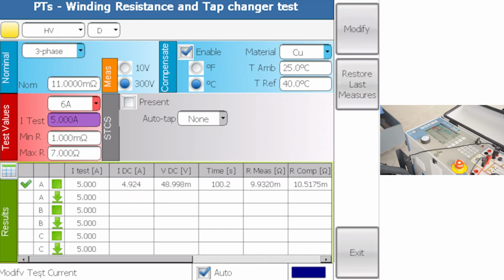All right, we've measured the resistance. So the measured resistance is 9.9, very close to what I expected. The compensated resistance is 10. Compensated means that if you measured at 25, which is the temperature right now, what would be the resistance measured at 40 degrees Celsius? It would be slightly higher. So this is how we measured the resistance of phase A.